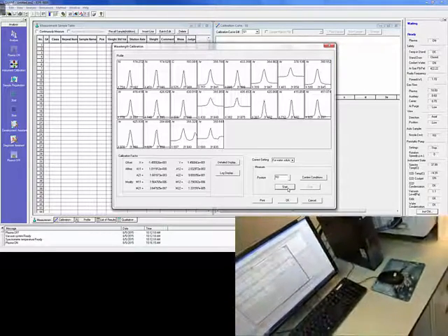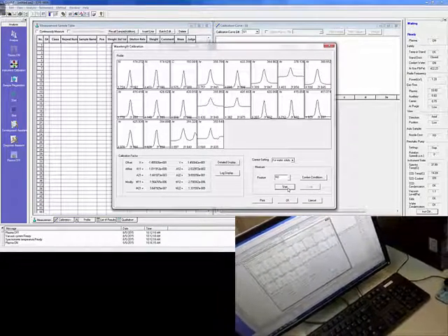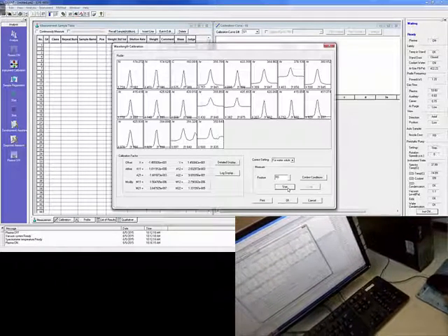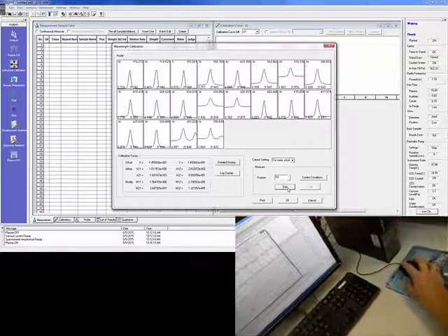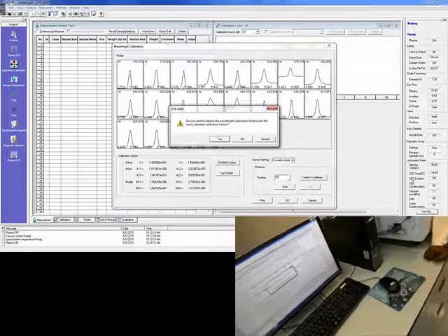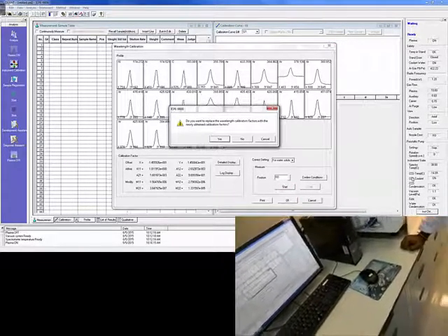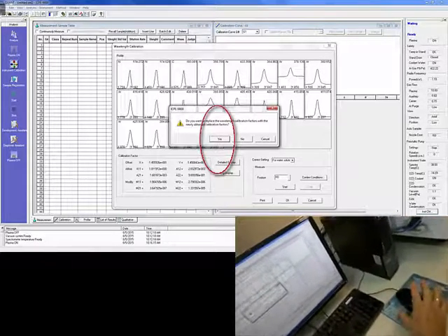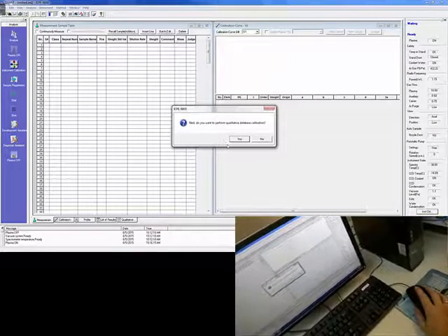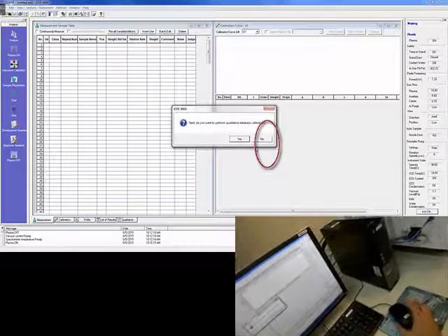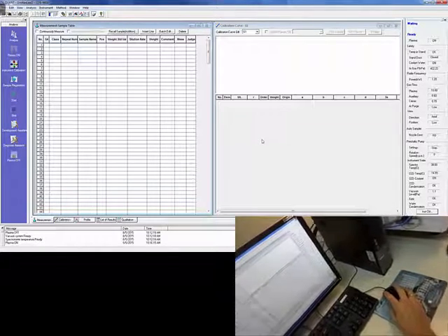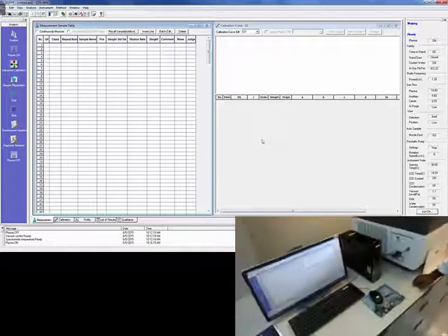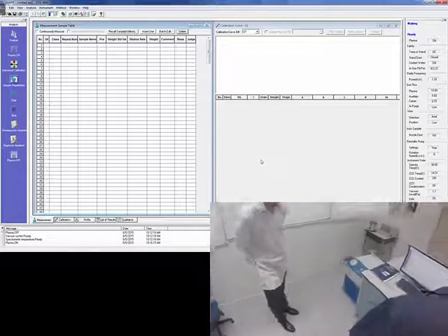Okay. So this process has now ended and you can see that the optimization on each of the various selected wavelengths has occurred. Providing your screen looks something like this, you can click OK. It now asks you, do you want to replace the existing calibration with this new one effectively? And so, of course, you need to answer yes. Next, do you want to perform a qualitative database calibration? The answer is no because hopefully we're being quantitative. Okay. So we end up with a screen that looks like this.